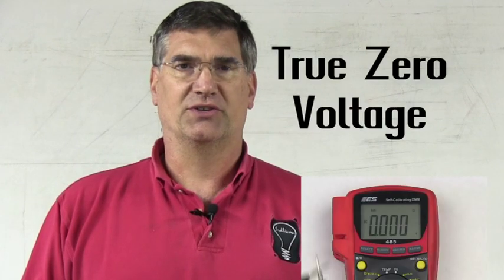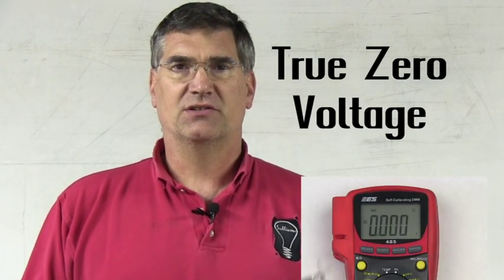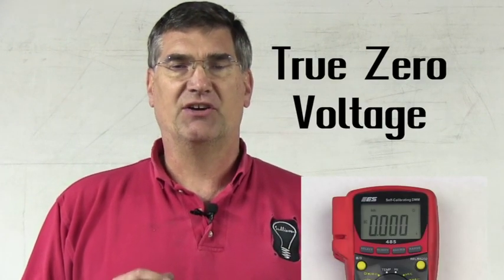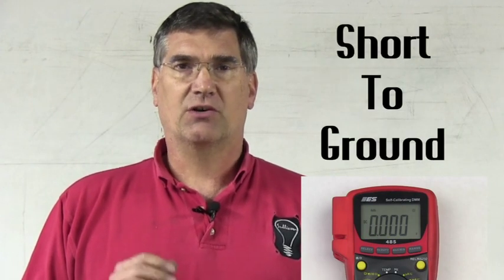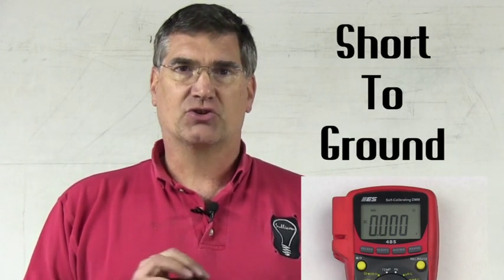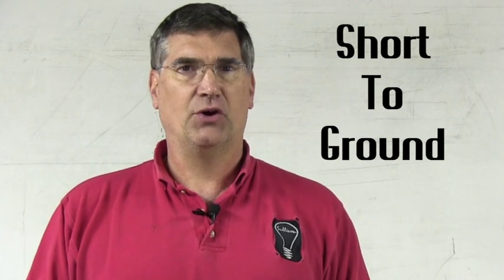So when you're reading voltage, if you see ghost voltage, then the immediate indication is that you have an open circuit, and that's the name of the fault, and that's what you need to go look for. Additionally, the meter will also show straight zero voltages or true zero voltage. True zero voltage is an indication of a short to ground. So a short to ground is going to show up as straight zeros when you're trying to read voltage.